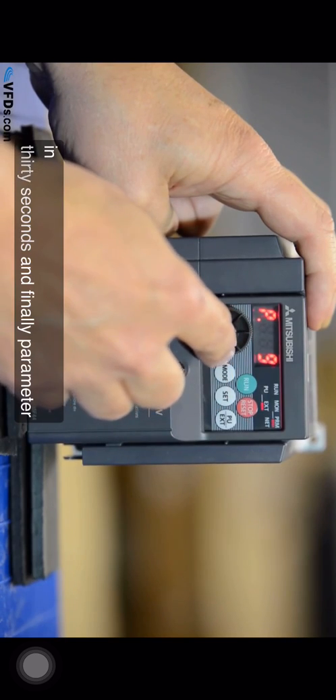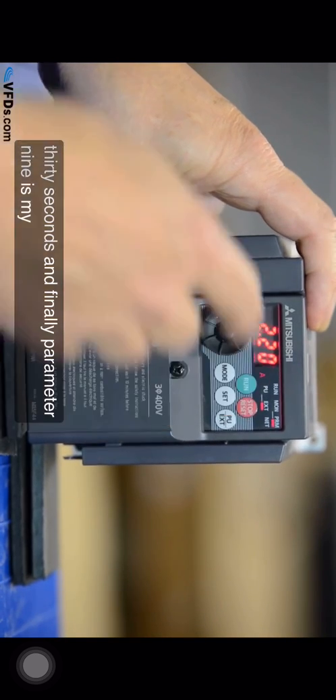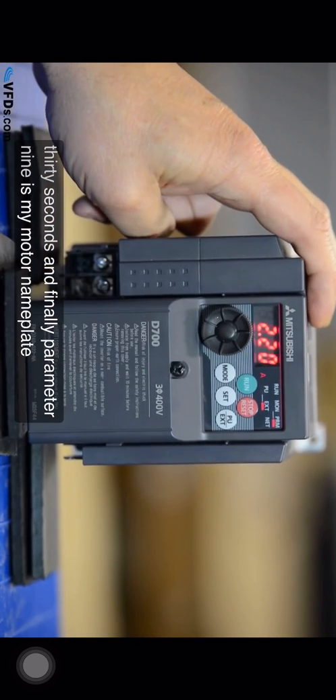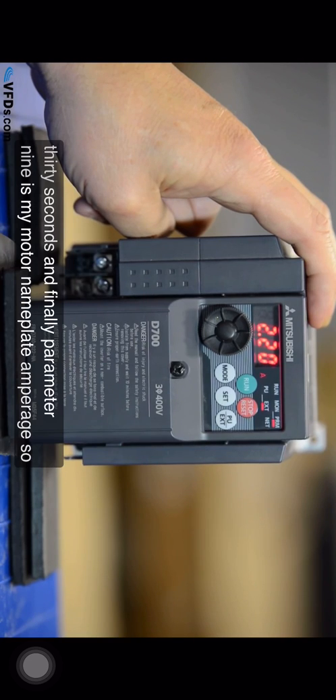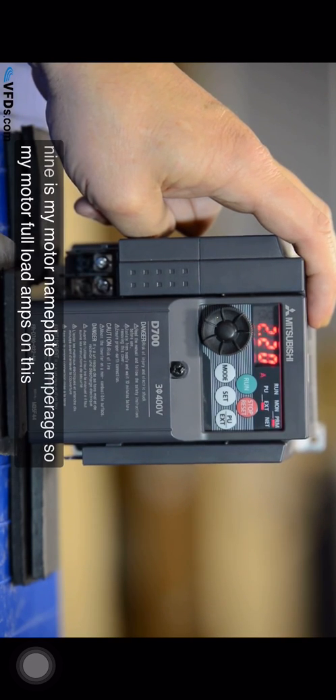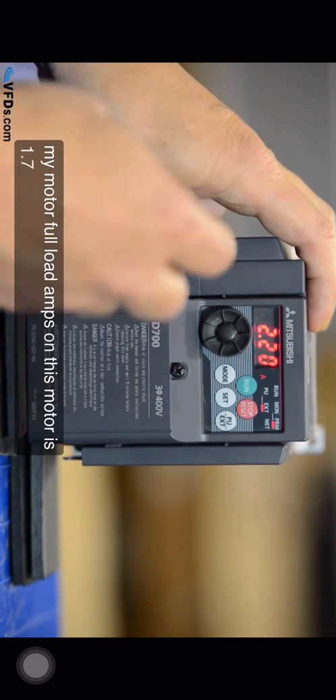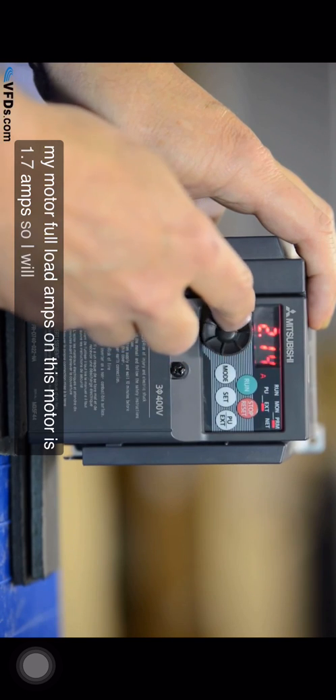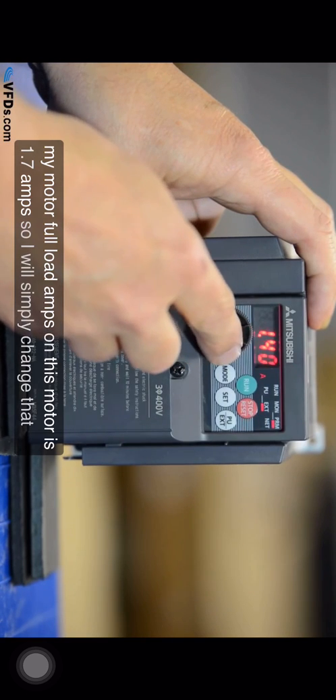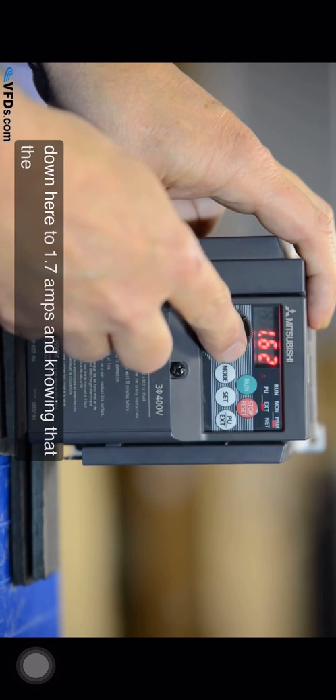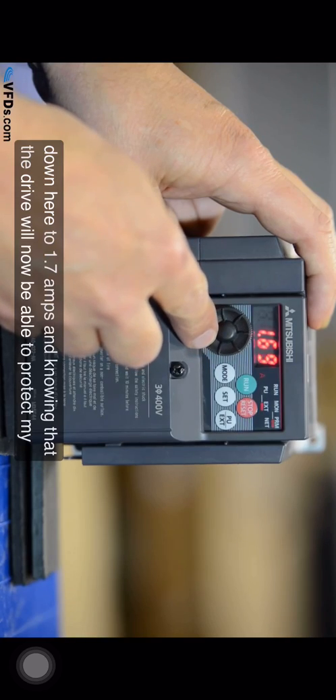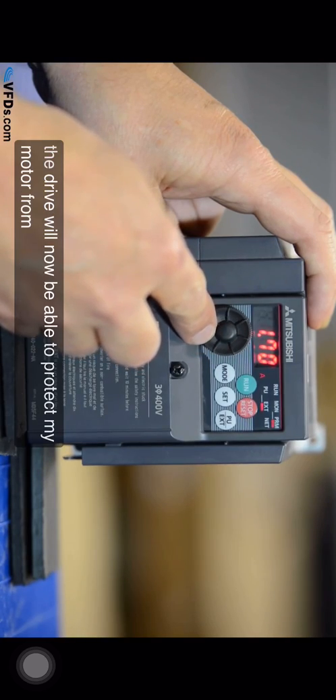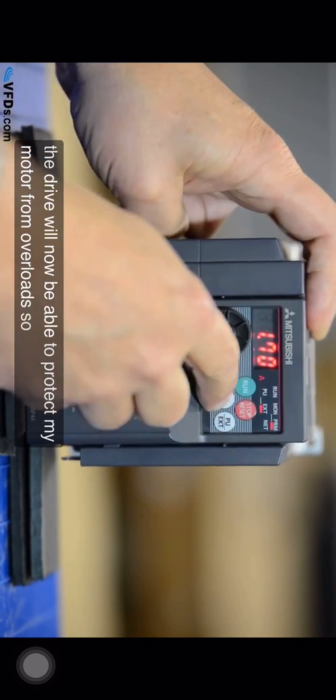And finally parameter nine is my motor nameplate amperage. So my motor full load amps on this motor is 1.7 amps. So I will simply change that down here to 1.7 amps, knowing that the drive will now be able to protect my motor from overloads.